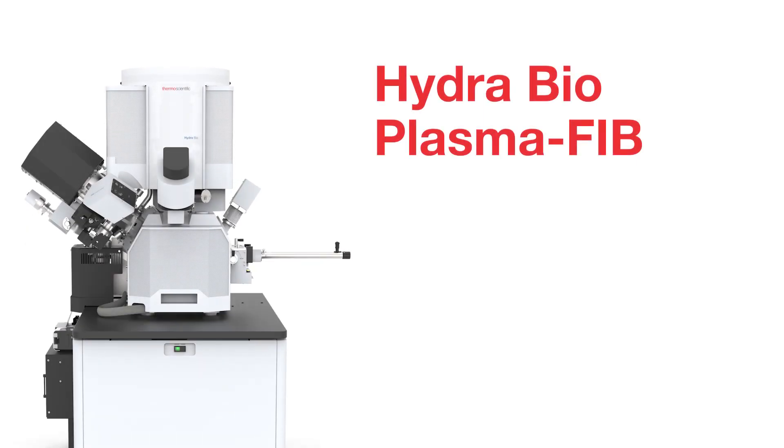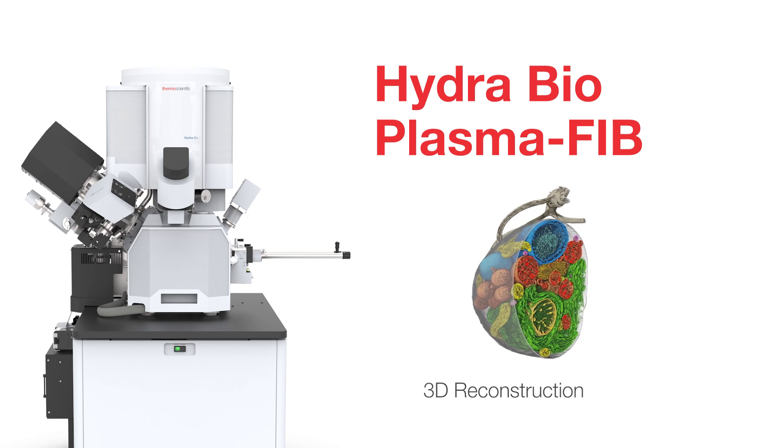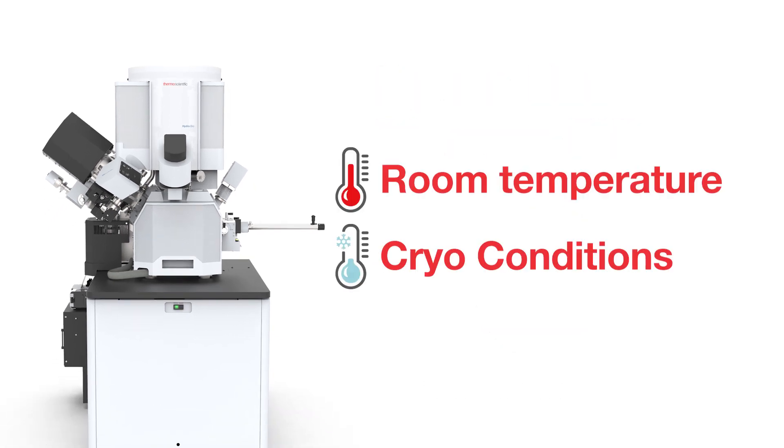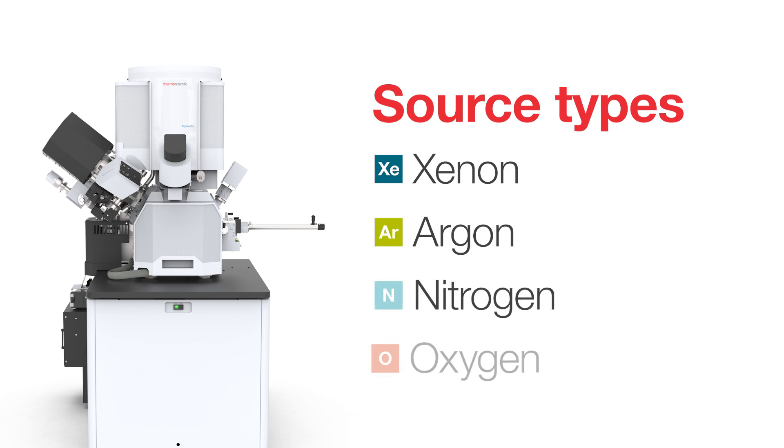The Thermo Scientific Hydra Bio Plasma-FIB is a versatile tool for high-throughput cellular FIB-SEM tomography, capable of operating at both room temperature and cryogenic conditions. The instrument uses a plasma-focused ion beam with a switchable ion source and 4 different ion species to match the right application.